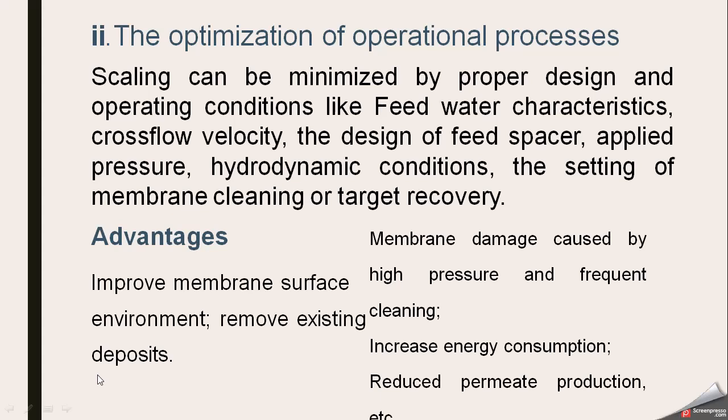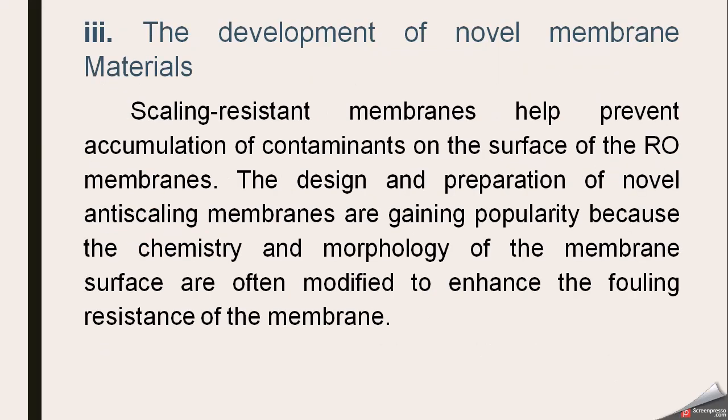When we establish a cleaning frequency, the deposits which are already fixed on the membrane will be removed. The disadvantages are that membrane damage can be caused by high pressure or frequent cleaning, and increased energy consumption. Permeate production is also reduced if you reduce the applied pressure.